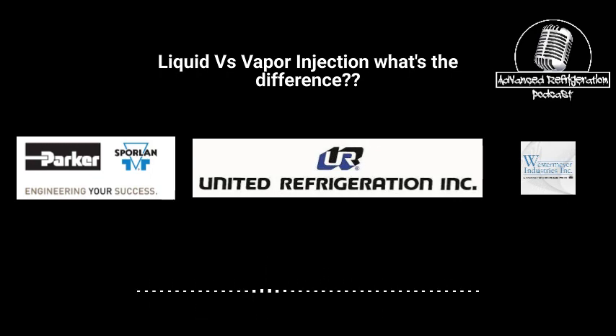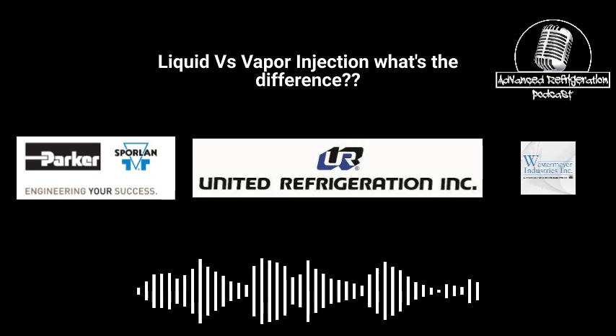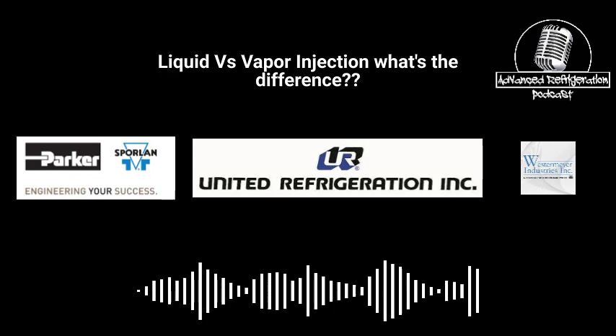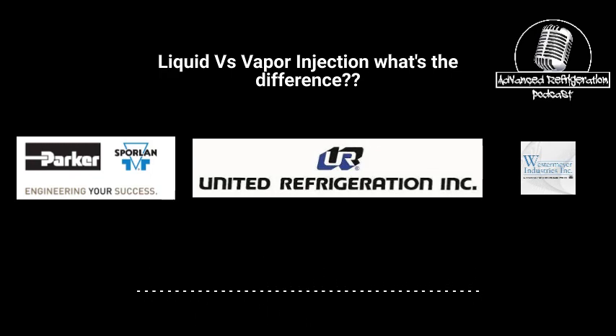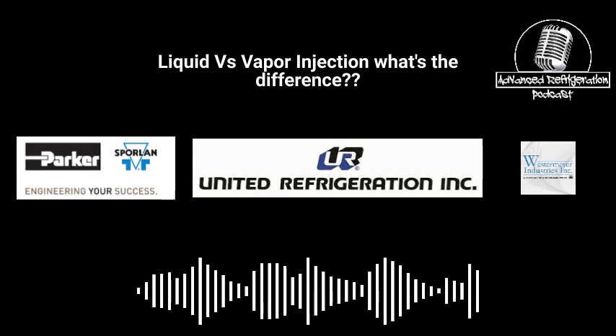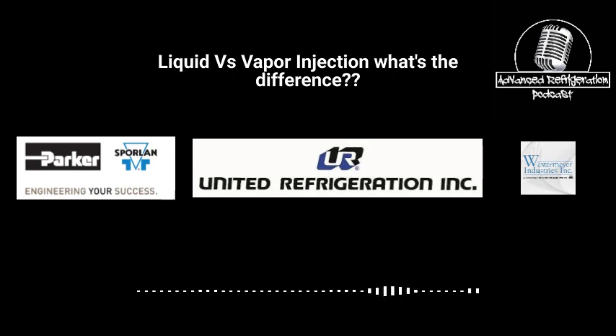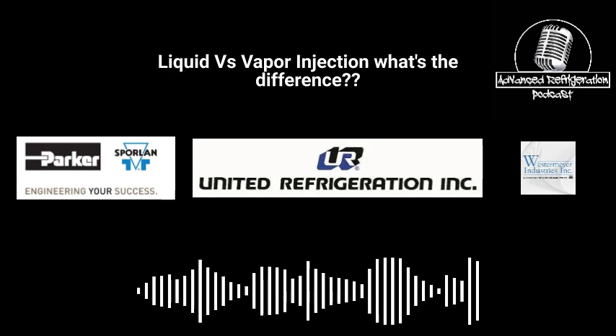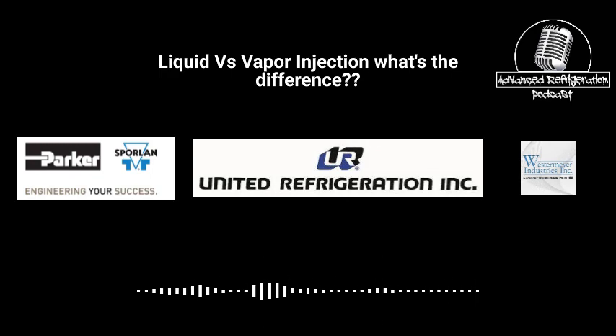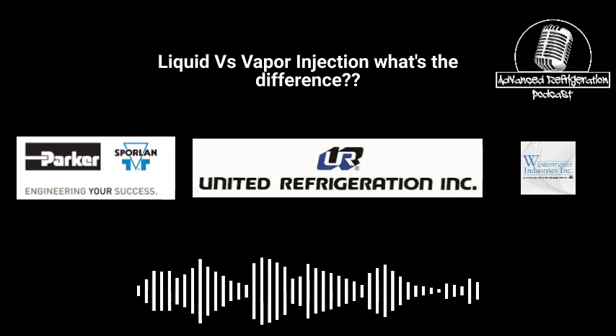Yeah, I mean, it is interstage pressure. It is technically your interstage pressure, and scrolls have it for vapor injection, screws have it, compound compressors have it. Now, that is essential for that interstage pressure to have that subcooler working. It derates that compressor a lot. A lot of guys won't pay attention to it. A lot of subcoolers won't be working, and that interstage pressure is all over the place, because now your interstage pressure is only coming from your suction and discharge of that compressor.